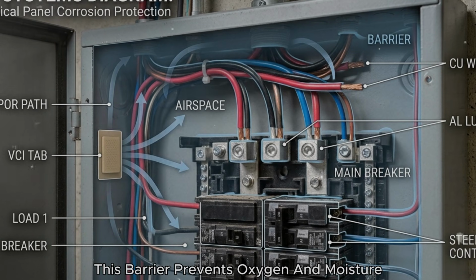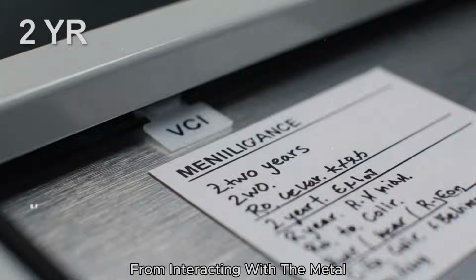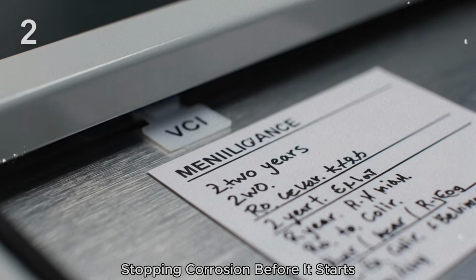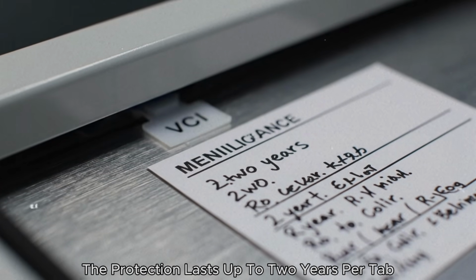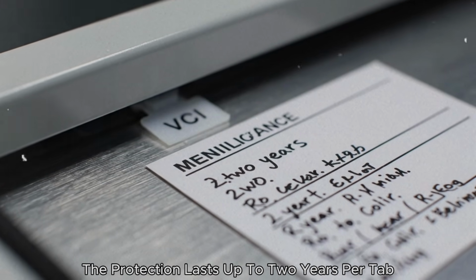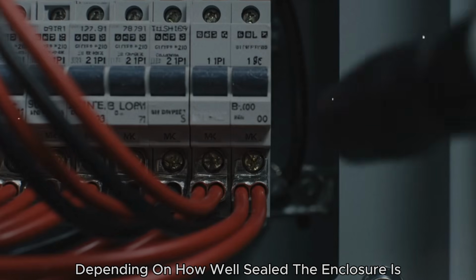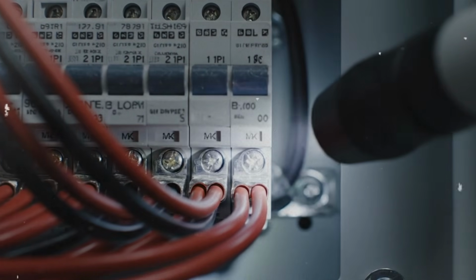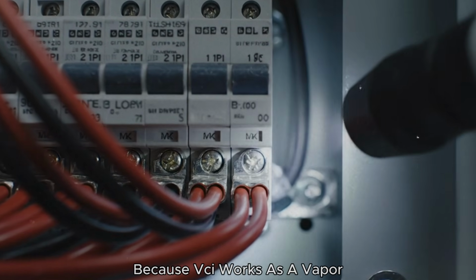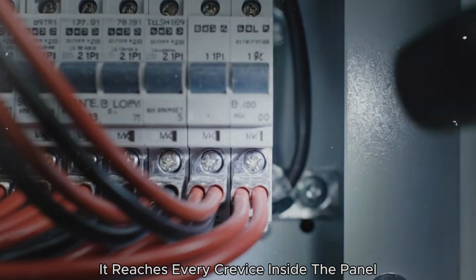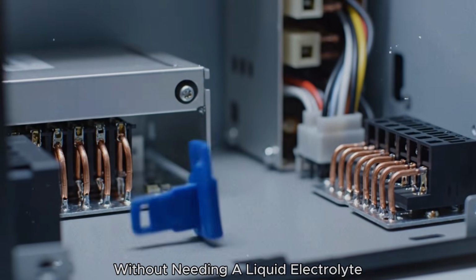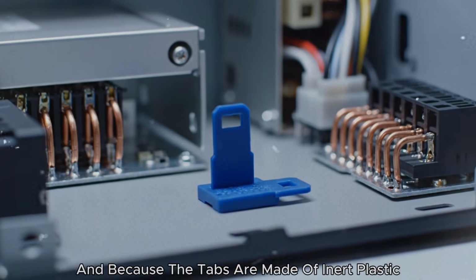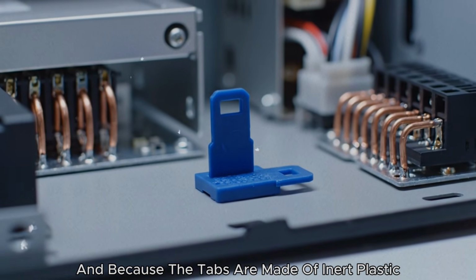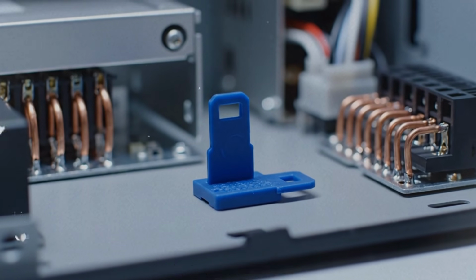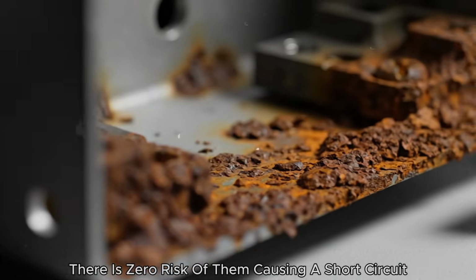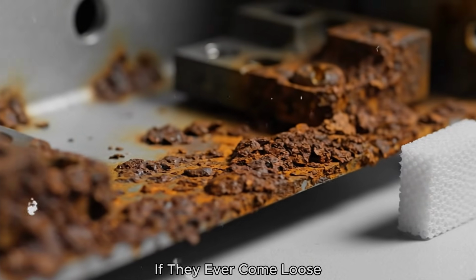This barrier prevents oxygen and moisture from interacting with the metal, stopping corrosion before it starts. The protection lasts up to 2 years per tab, depending on how well sealed the enclosure is. Because VCI works as a vapor, it reaches every crevice inside the panel without needing a liquid electrolyte. And because the tabs are made of inert plastic and chemical compounds, there is zero risk of them causing a short circuit if they ever come loose.